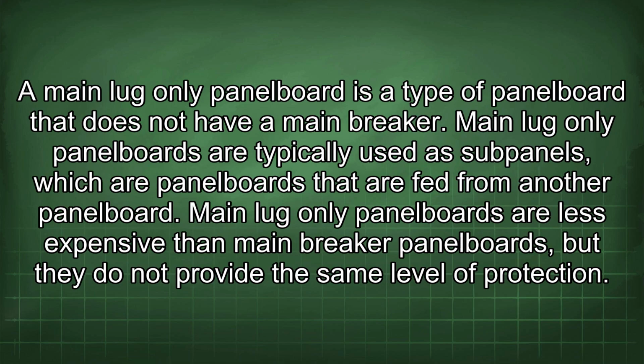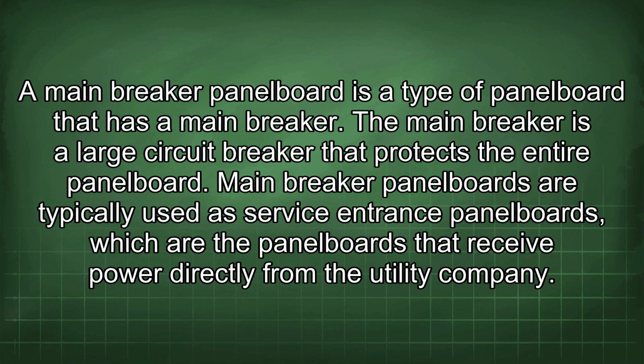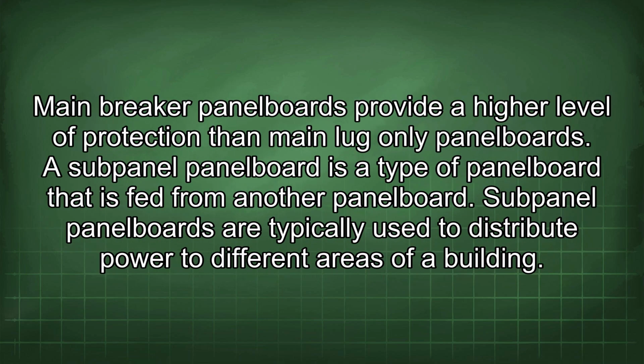The type of panel board that is best for a particular application will depend on the specific requirements of the electrical system. A main lug-only panel board is a type of panel board that does not have a main breaker. Main lug-only panel boards are typically used as sub-panels, which are panel boards that are fed from another panel board. Main lug-only panel boards are less expensive than main breaker panel boards, but they do not provide the same level of protection. A main breaker panel board is a type of panel board that has a main breaker. The main breaker is a large circuit breaker that protects the entire panel board. Main breaker panel boards are typically used as service entrance panel boards, which are the panel boards that receive power directly from the utility company. Main breaker panel boards provide a higher level of protection than main lug-only panel boards.